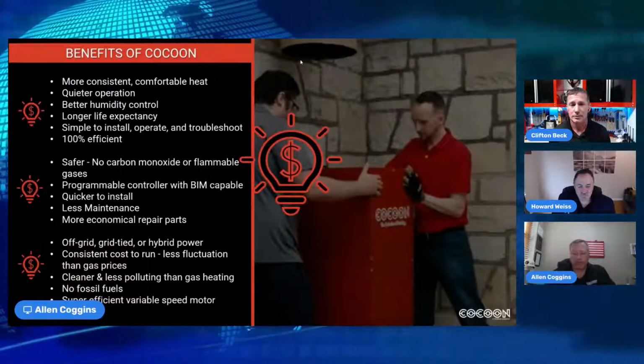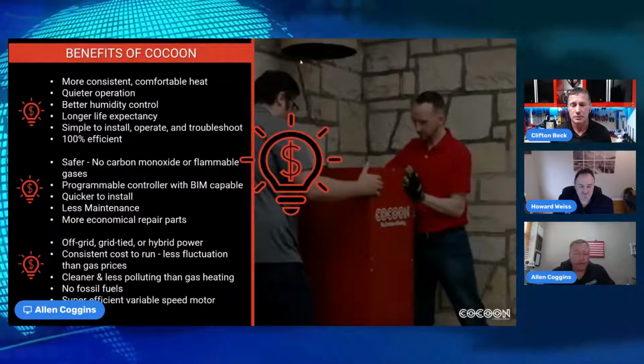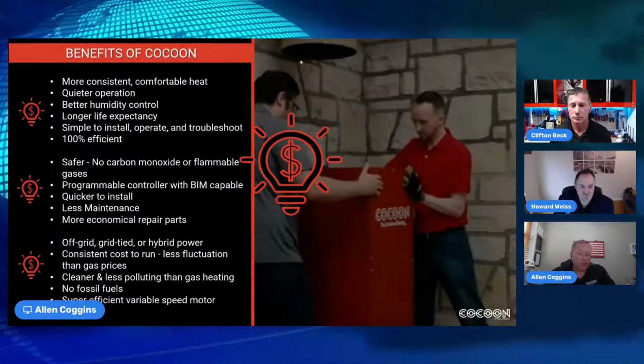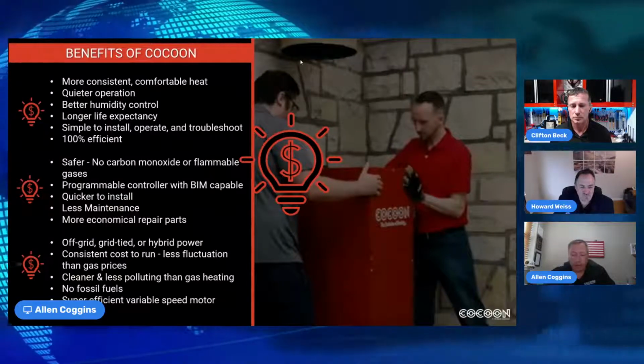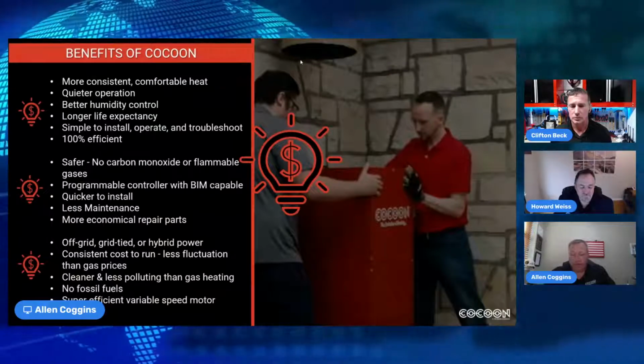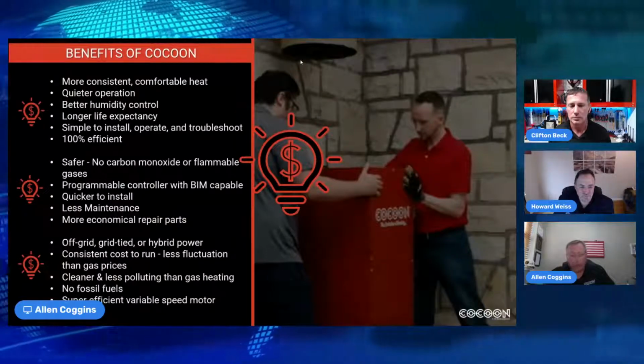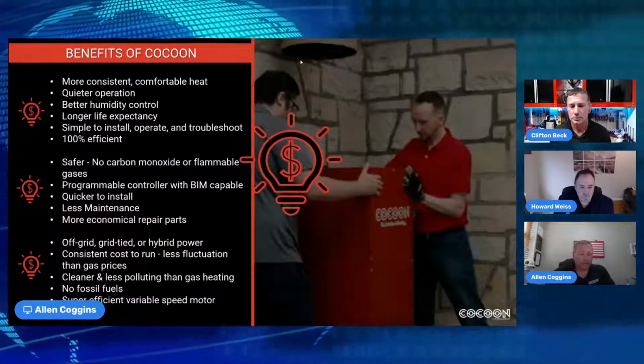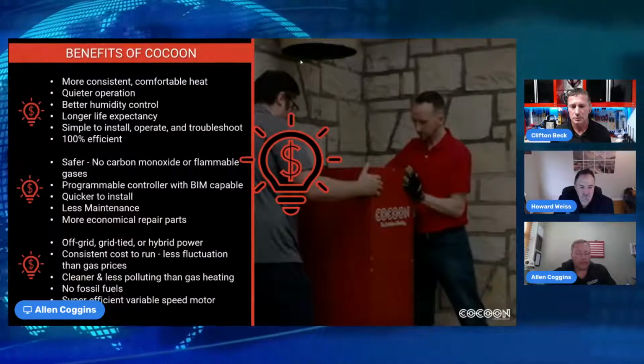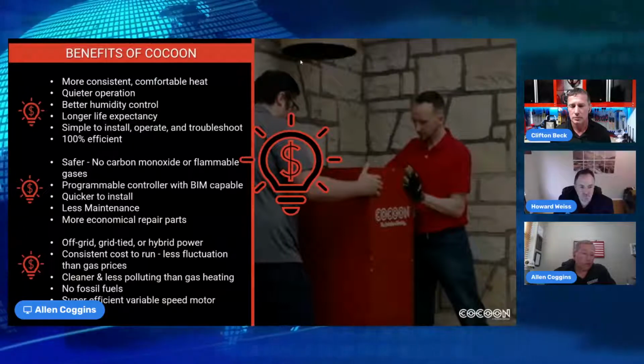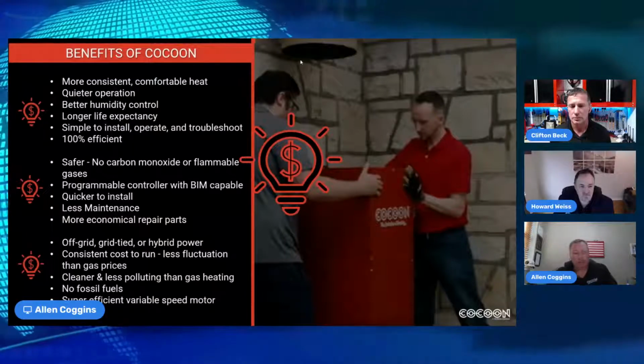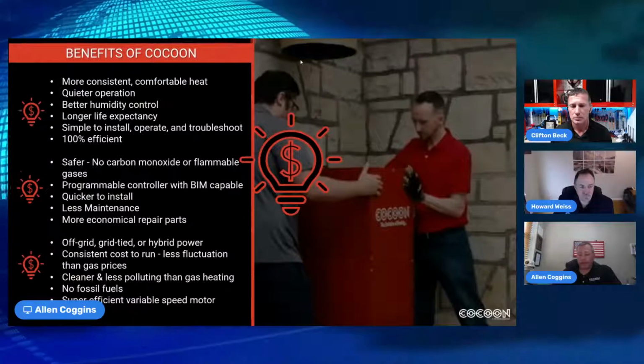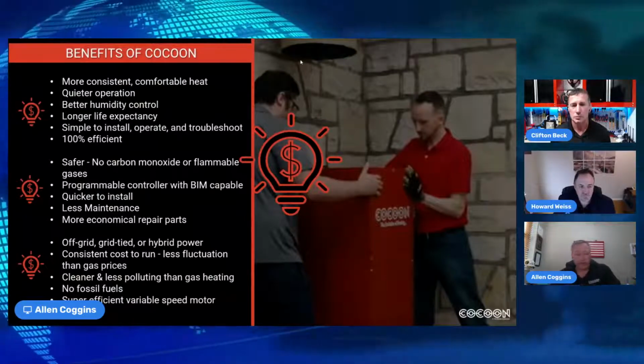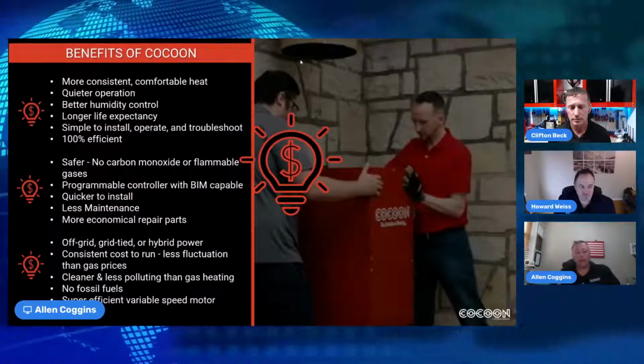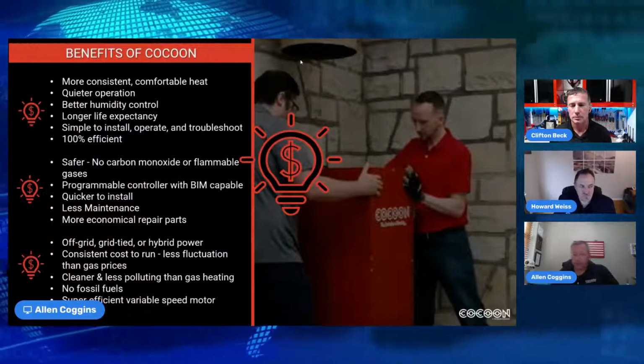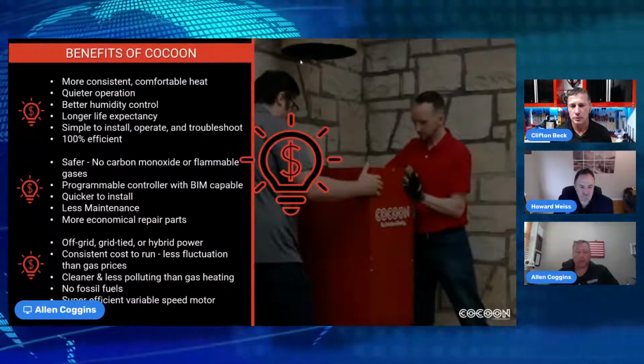We've matched with pretty much everybody's condenser or coil, it doesn't matter, name a brand, I've tried to hit all the major ones. When I say matched, you can use our furnace with their A coil and condensing unit. Of course, we want to know what they're running at, meaning are they running 400 CFM per ton, or 350 for better dehumidification, or in high velocity systems some are running 250 per ton when you get right down to it.